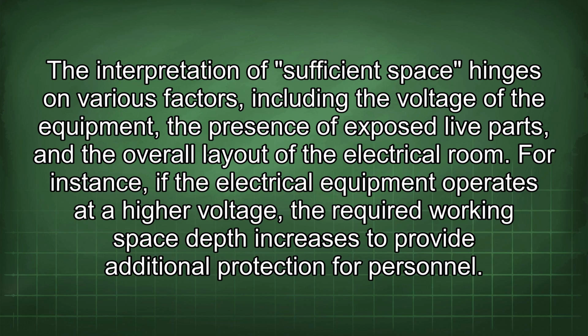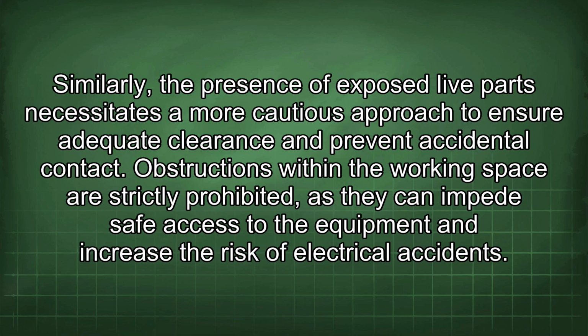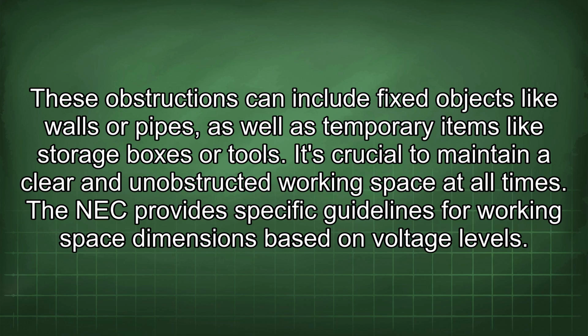The interpretation of sufficient space hinges on various factors, including the voltage of the equipment, the presence of exposed live parts, and the overall layout of the electrical room. For instance, if the electrical equipment operates at a higher voltage, the required working space depth increases to provide additional protection for personnel. Similarly, the presence of exposed live parts necessitates a more cautious approach to ensure adequate clearance and prevent accidental contact. Obstructions within the working space are strictly prohibited, as they can impede safe access to the equipment and increase the risk of electrical accidents. These obstructions can include fixed objects like walls or pipes, as well as temporary items like storage boxes or tools. It's crucial to maintain a clear and unobstructed working space at all times.